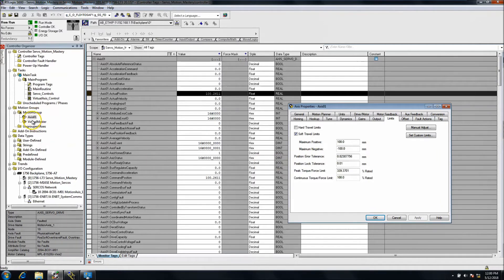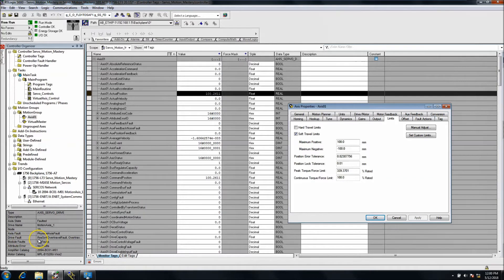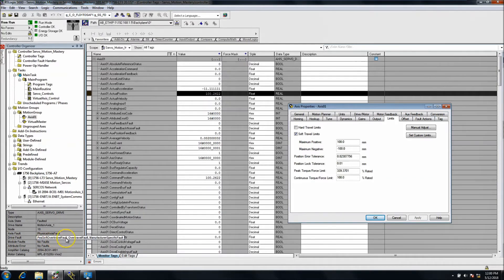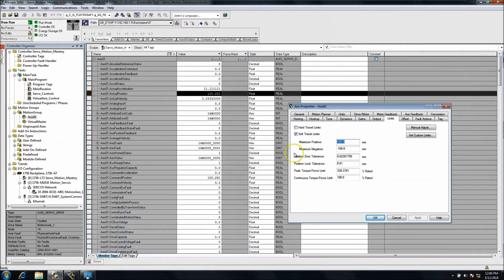Down here in the fault it says axis fault, physical axis fault, and then it says drive fault. The drive fault is a positive soft over travel. So that means the maximum positive over travel that I had set to 100, it exceeded 100 right here and that's what caused the problem.